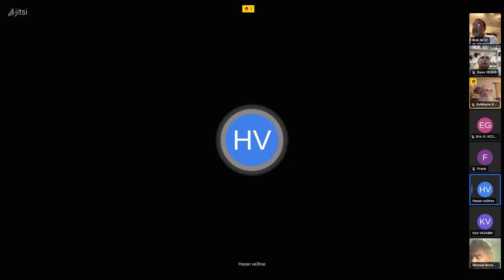So S11 is the reflected value on port one? Yes, on S11 you'd measure SWR, for example. It basically measures - it looks at the output of the VNA itself, into the device and the antenna, and looks at the reflection coming back. That's what S11 is, the ratio of those. That's all done on port channel zero, the top one.